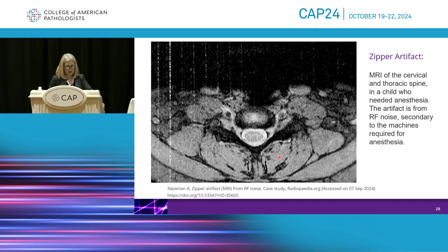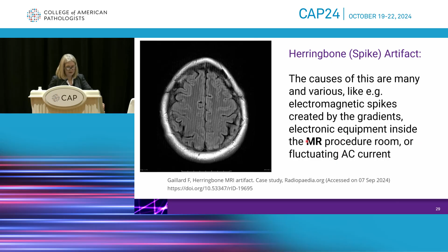And another issue is the herringbone artifact, also known as a spike artifact. Usually this is caused by some kind of spike in the electromagnetic field, either generated by the gradient magnets, or some type of electronic equipment within the MR room can cause this, or even a fluctuating current.